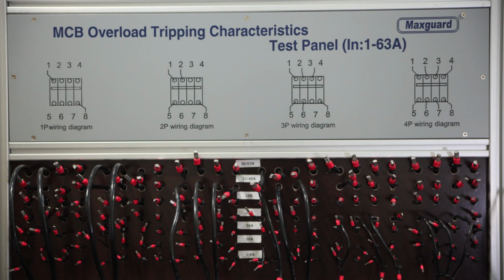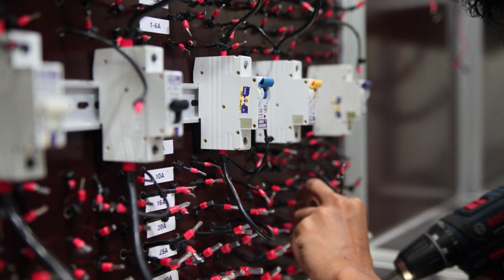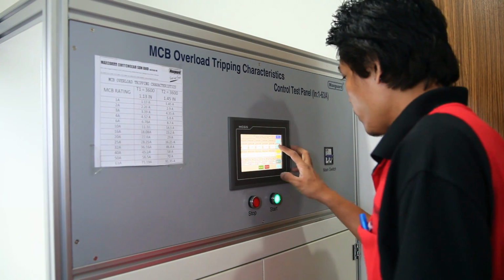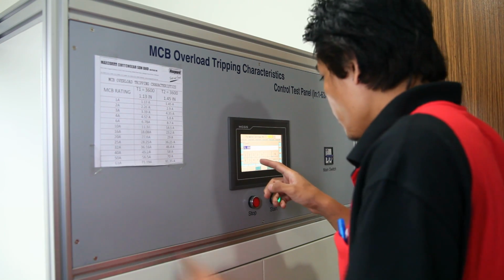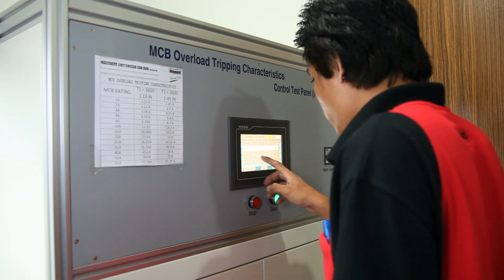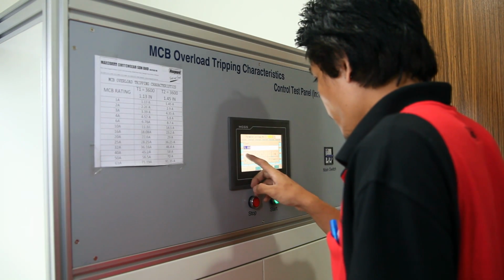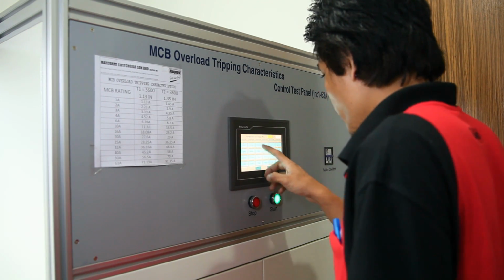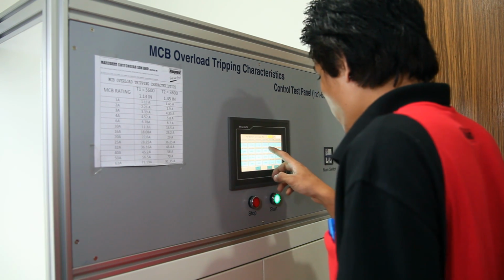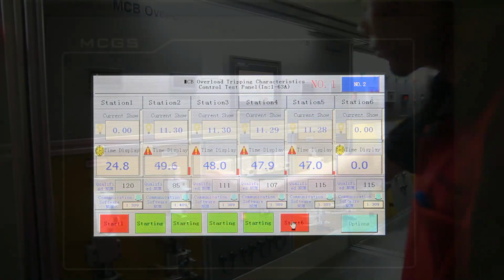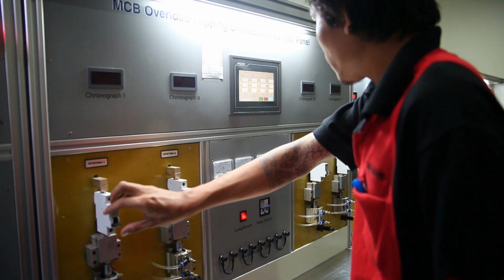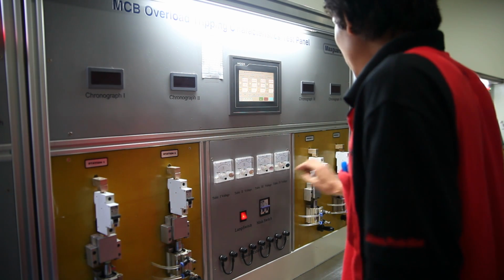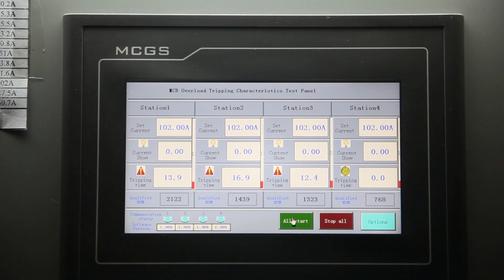Overload current tripping test for MCBs. MCBs are tested pole by pole, irrespective of tripping characteristics type B, C or D. Testing for this requirement is purely to verify thermal characteristics. A current of 1.13 times is injected for a specific time, followed immediately with ramping up the current within 5 seconds to 1.45 times for tripping. For additional current of 2.55 times, tripping must occur within 60 seconds for MCBs rated up to 32 amperes and 120 seconds for ratings above 32 amperes.